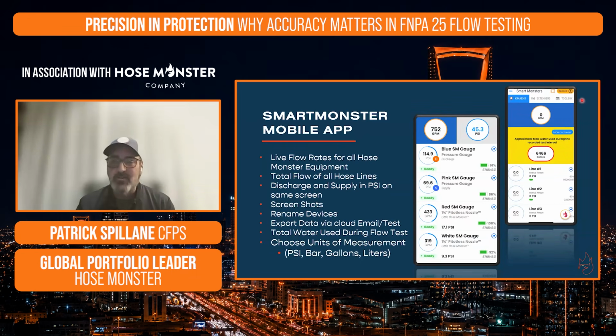We can record each session as well. We can bring that data directly into an Excel spreadsheet to document our flow tests. And that recording is also going to work as a water consumption meter. So we can document how much water we are using in total during our test, especially if we're doing a hydrant test, we can now know how much water we flowed total during that test. And the great thing about it is it's a universal gauge. So we can go into our settings and display bar pressure versus PSI, or liters per minute or liters per second versus gallons. We can set all that up in our settings. So it's very adaptable to any region of the world, depending on how you like to take your units of measurement.